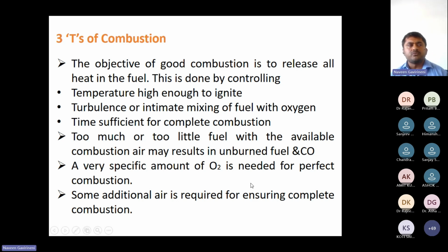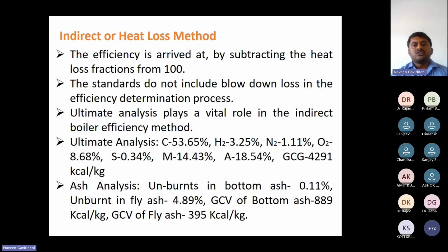To ensure complete combustion, we have an excess air arrangement, and the OEM also gives an excess air concept. For boilers, as per the capacity, size and type of boiler, they provide 15 to 30% excess air. On CFBC we get 20 to 25%, while for PF, pulverized fuel, it is 15 to 20% only. So these are the indirect heat loss methods. There are two here. After getting the heat losses, we subtract them from 100 and get the boiler efficiency.